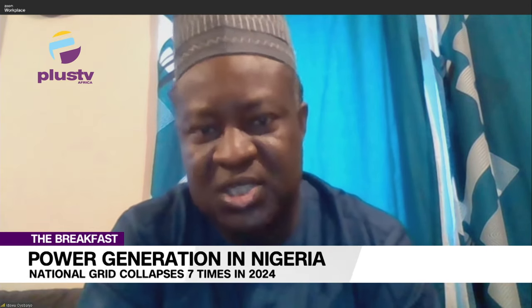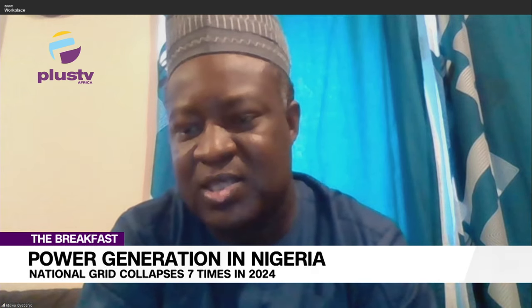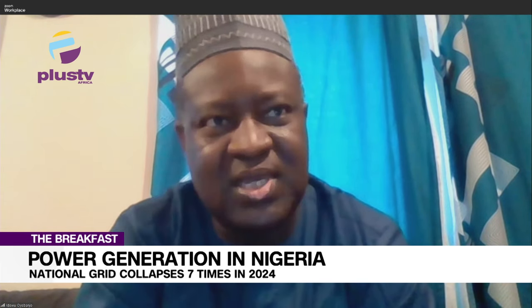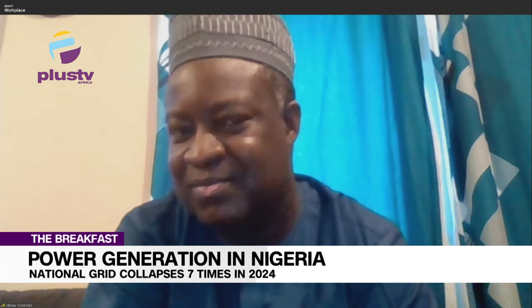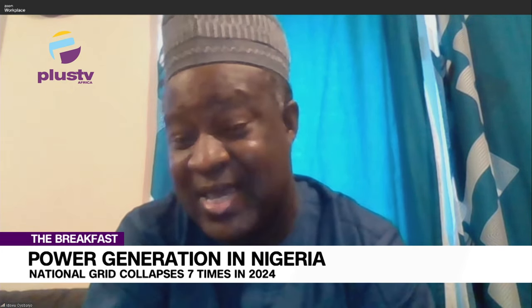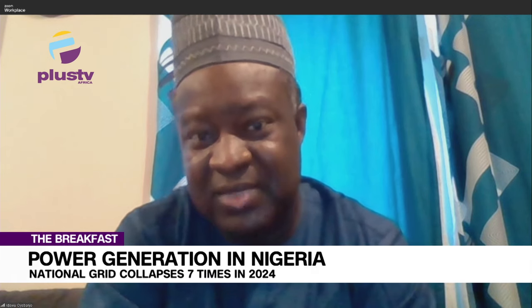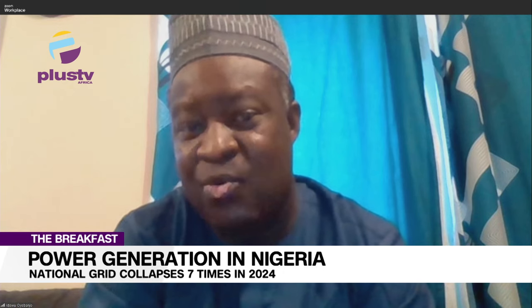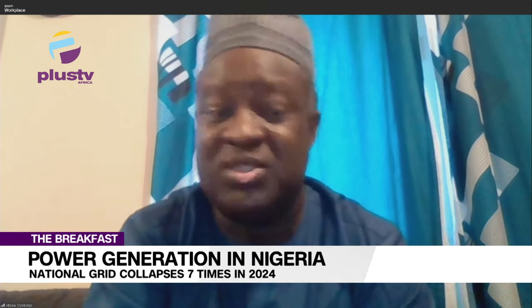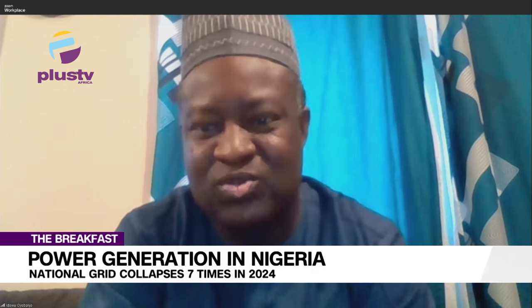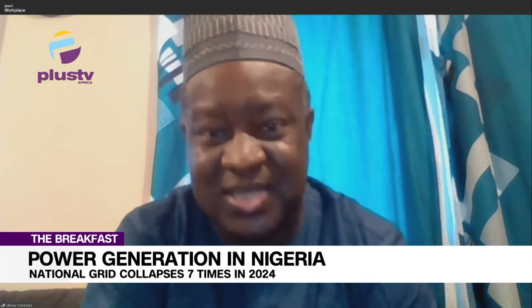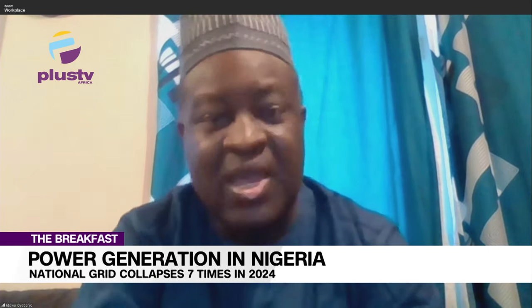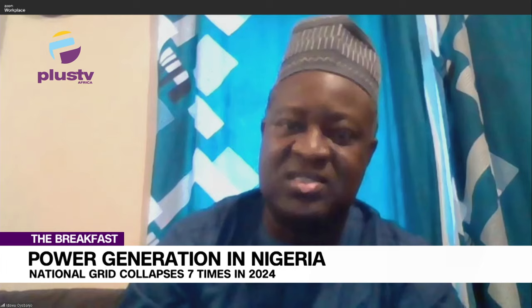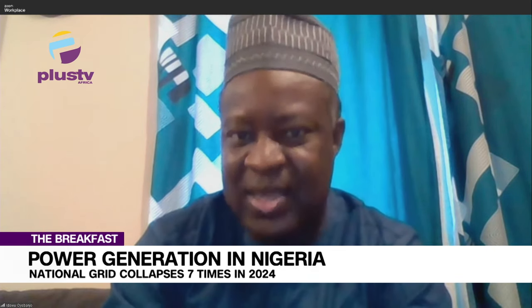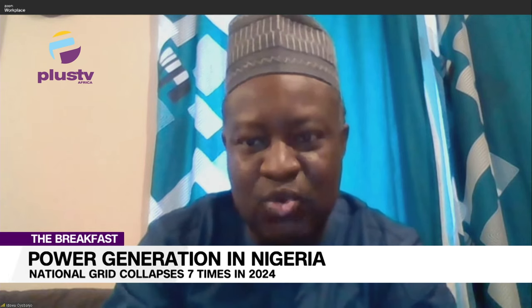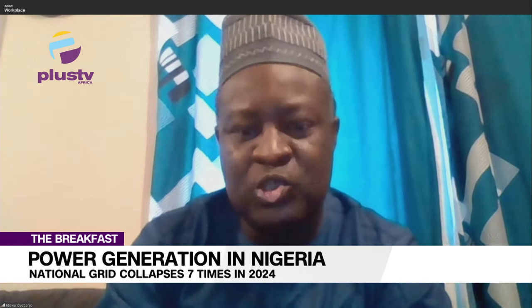The other issue is there is no proper monitoring, supervisory control and data acquisition system. Since 1990 we've been hearing about SCADA in Nigeria, and it has never materialized up to today. There's one recently sponsored by the World Bank, and hopefully that will come on stream in 2025. But it's sad that over 20, 30 years we've been hearing about SCADA in Nigeria. SCADA means Supervisory Control and Data Acquisition System, which means operators can see when a fault is developing and see the flows. If it's happening in Calabar, they'll quickly see it on their computer and can act, for example opening the circuit breaker so it doesn't affect the rest of the system.